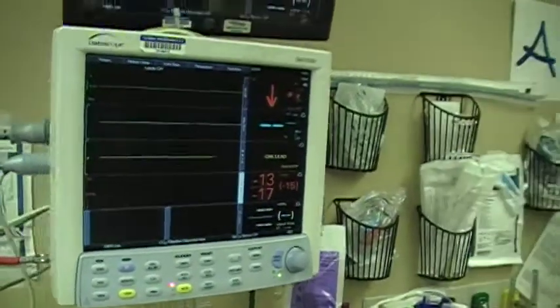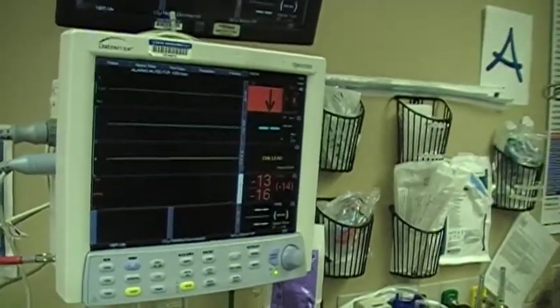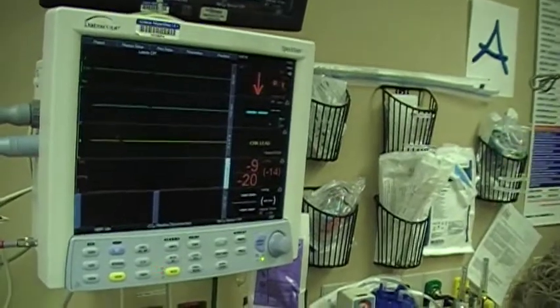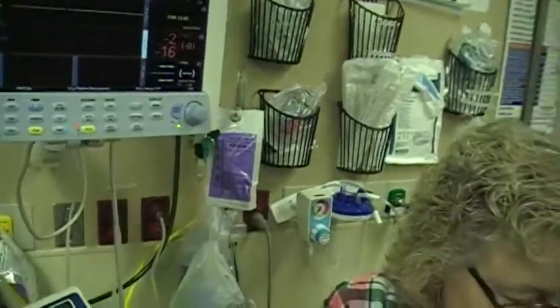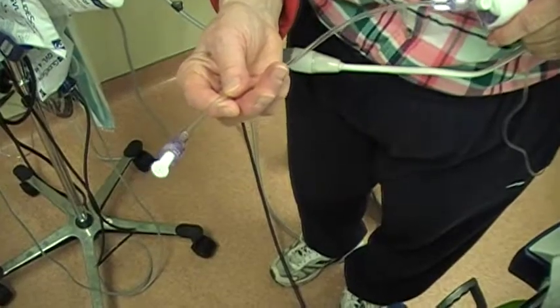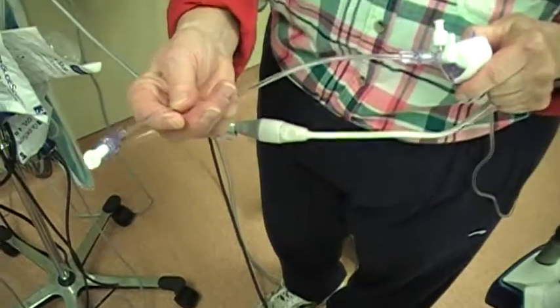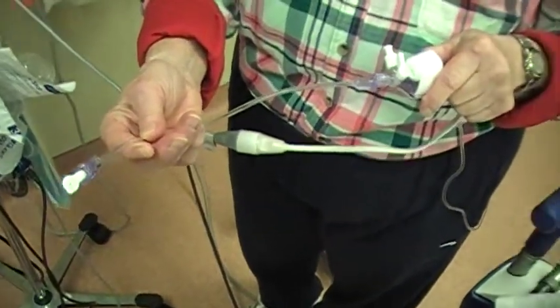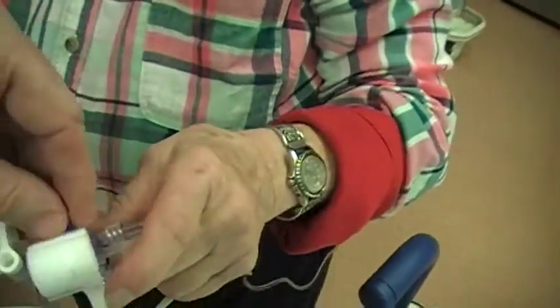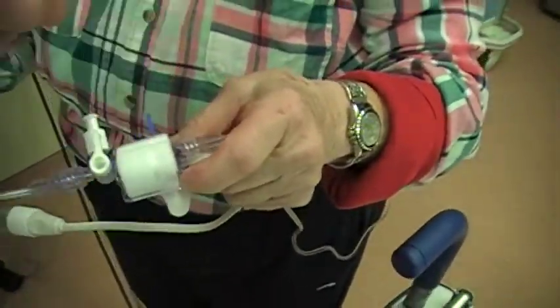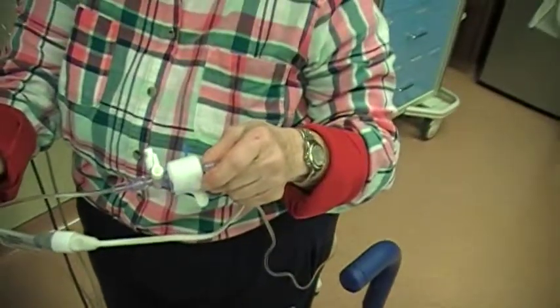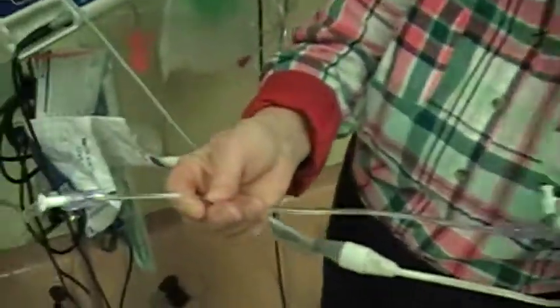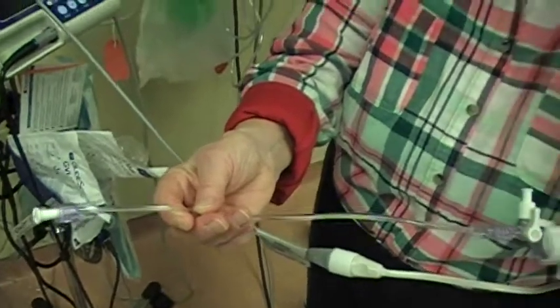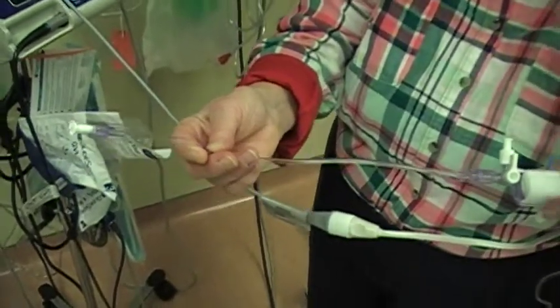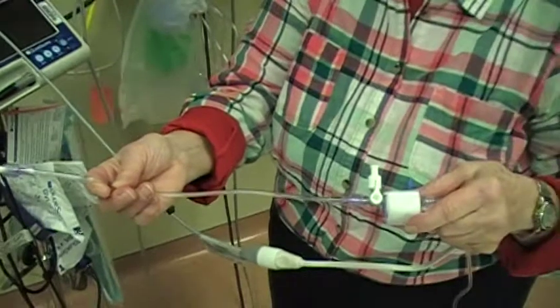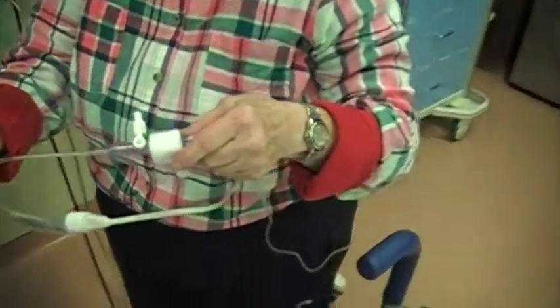At this point, you're basically going to wait for the physician to go ahead and place the line. Once he's placed the line, you will hand him the end that goes to the patient. And what I would recommend is that when you do that, before he hooks it up, you pull on this little blue tab while he is inserting it into the arterial. Therefore, it eliminates any air getting caught between the end of your tubing and the actual outflow of the blood of the arterial line. That is the basic setup of an arterial line monitoring system.